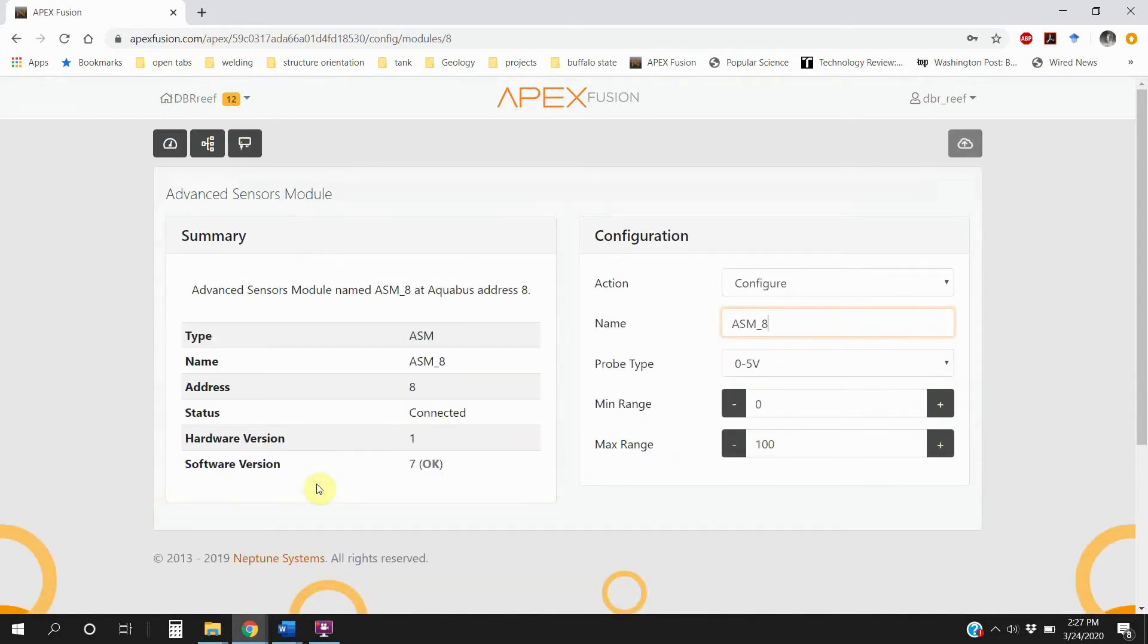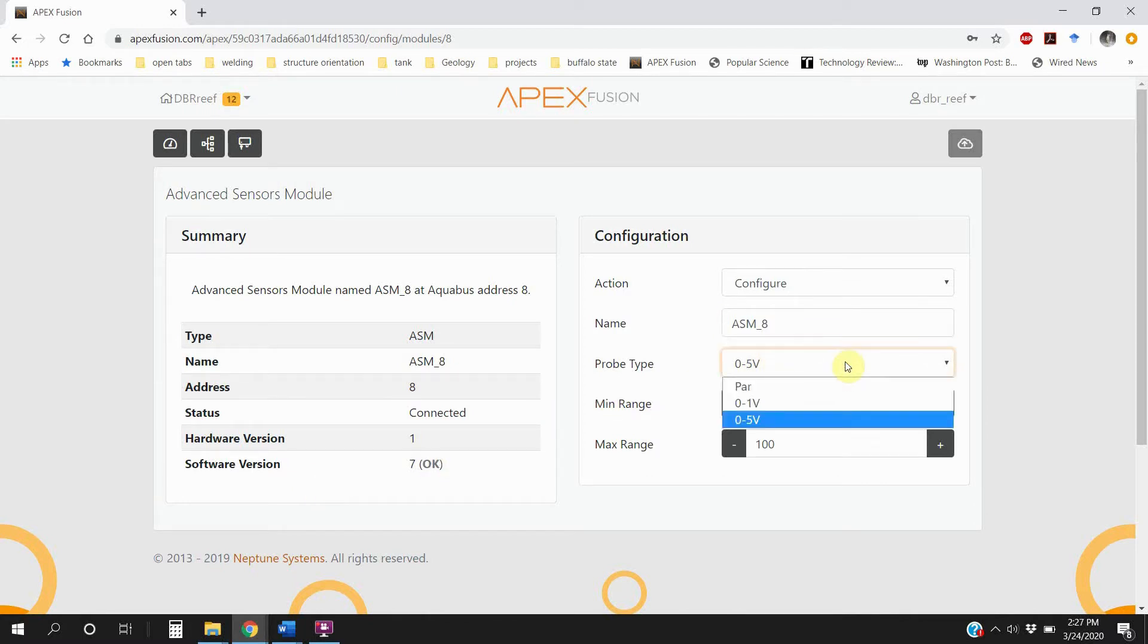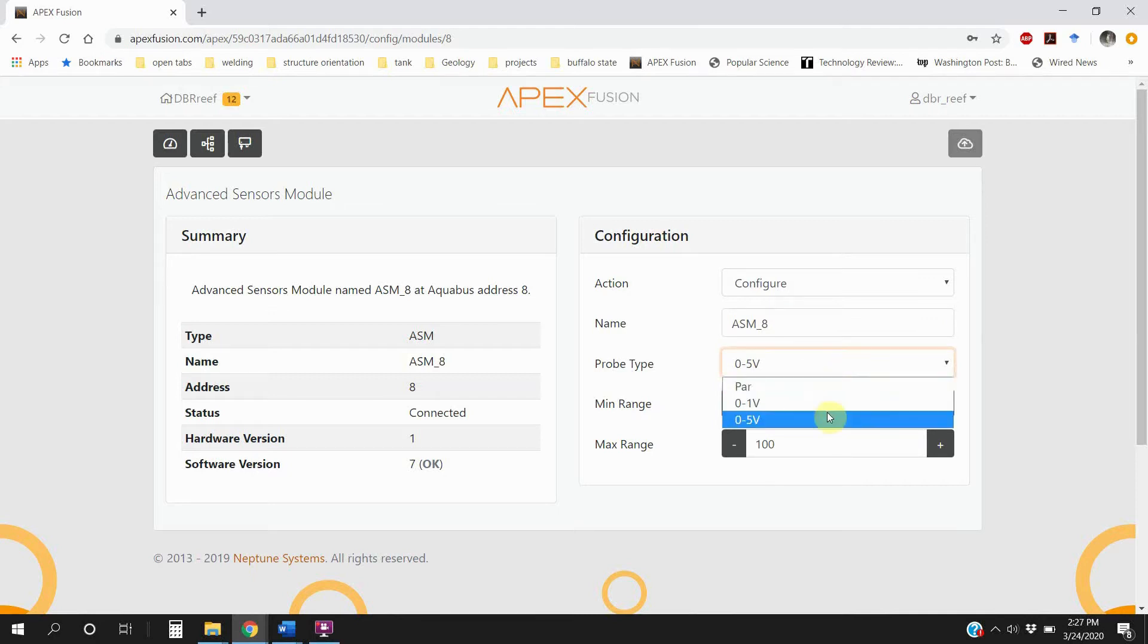And when you plug in your ASM module for the first time, it's probably going to have the probe type be PAR. And you want to set it to 0 to 5 volts. And then the min range should be around 0. If it's not, set it to 0.